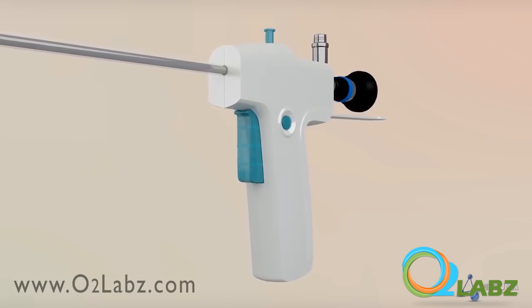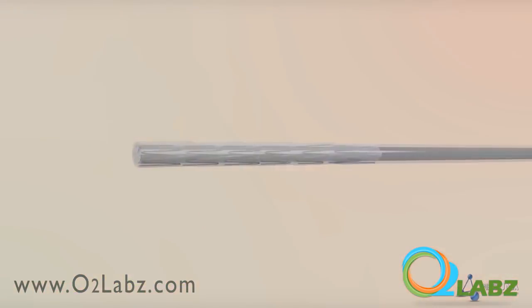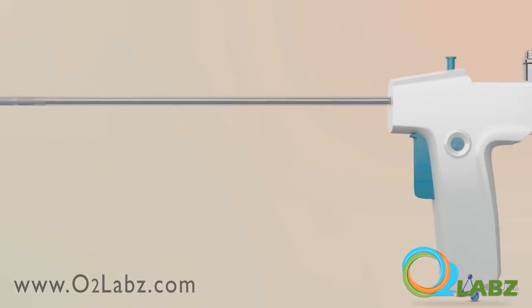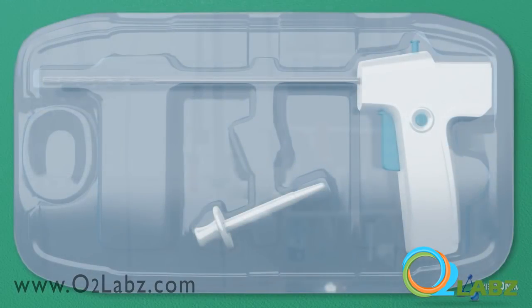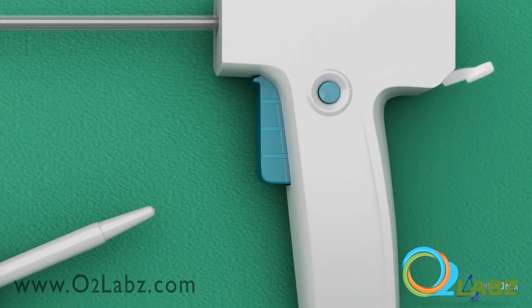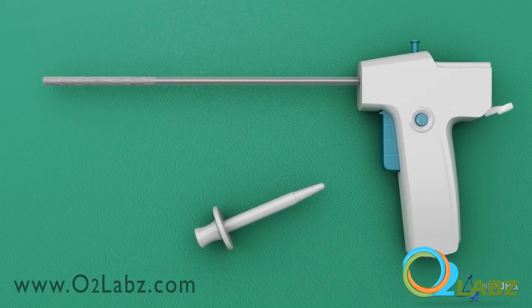The RPS is delivered using the one-platform delivery system, or OPS. This is a gun-style system that allows a streamlined and efficient endoscopic delivery. The delivery tool comes in a sterile, single-use pack with an RPS preloaded on the device. It has a green trigger and a green safety lock button, and is compatible with any 4mm optical element.